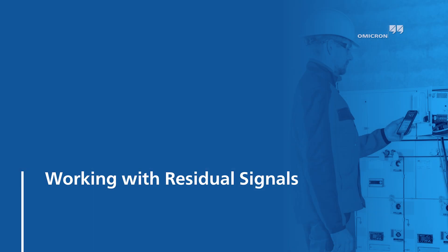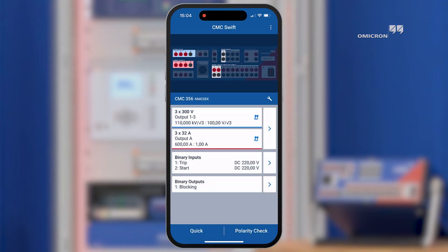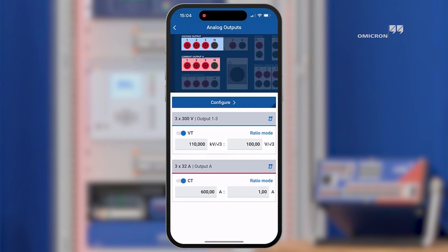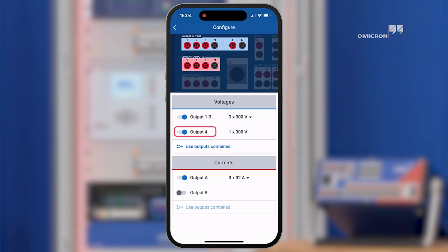The next feature worth mentioning is that the new update supports flexible routing of residual voltage and current signals. Let us have a look at how we can configure residual signals in CMC Swift. To begin, we must activate additional current and voltage outputs of the selected CMC test set.